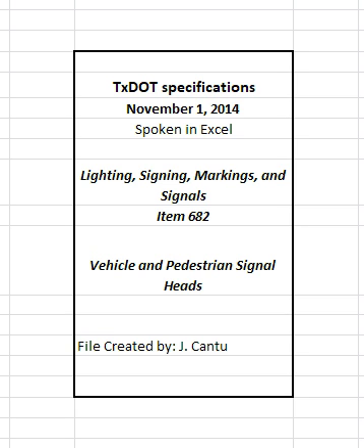Remove only the existing lens, reflector, and incandescent lamp when installing a retrofit replacement LED traffic signal or pedestrian signal lamp unit into an existing signal housing, fit the new unit securely in the housing door, and connect the new housing unit to the existing electrical wiring or terminal block by means of simple connectors.